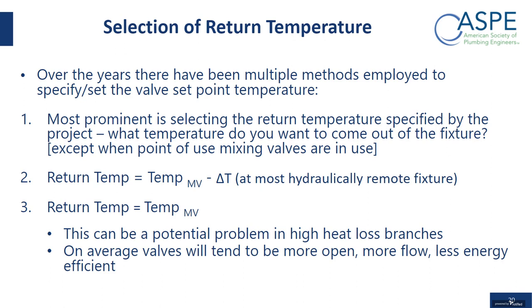If you're recirculating at, say, 140 degrees and you want 115 coming out, well, basically you're going to have a point of use mixing valve that knocks that 140 down to 115. And in that case, you would basically select a 140 set point for that system that you're recirculating at 140. The other way is basically determining the return temperature based on the temperature of your mixing valve minus your delta T. So if your mixing valve is at 120 degrees Fahrenheit and you have a delta T in the system of 5 degrees Fahrenheit, then that set point would be 115.